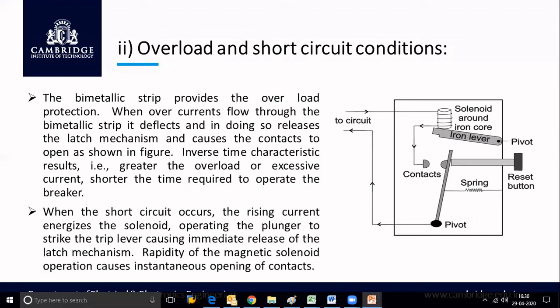So during overload conditions, the contacts will be opened by the bimetallic strip, and under short circuit conditions, the contacts will be opened by energizing the solenoid. These two mechanisms are used inside the MCB to protect the circuit from overload and short circuit conditions. These are the two main abnormal conditions which usually occur in any circuit.